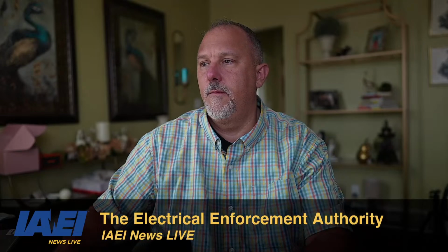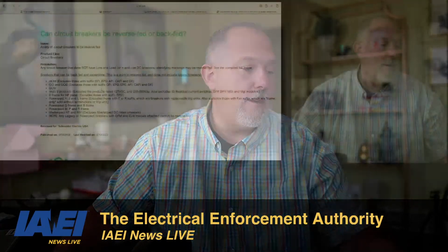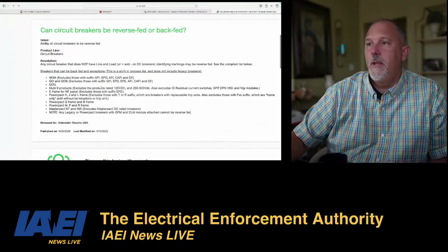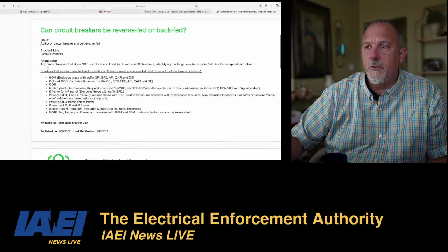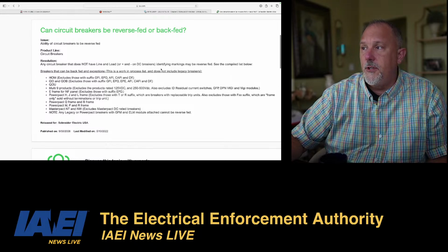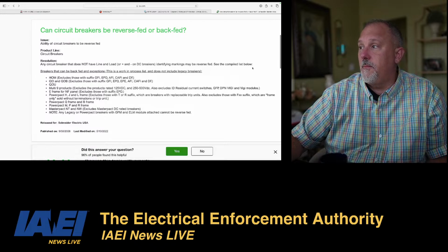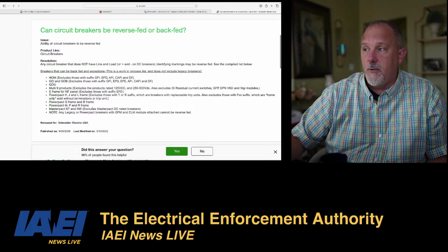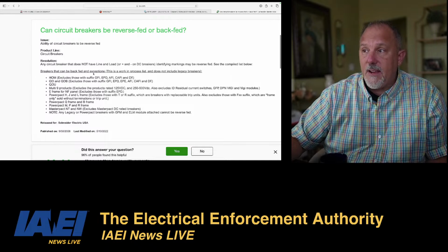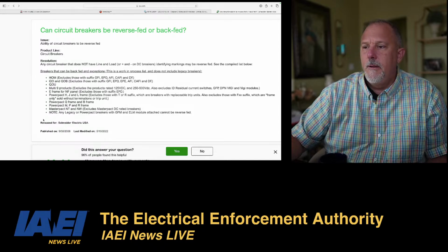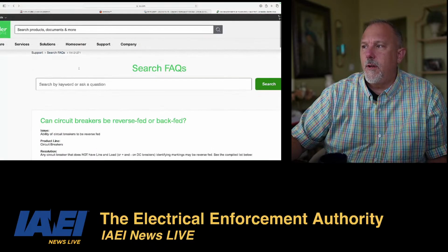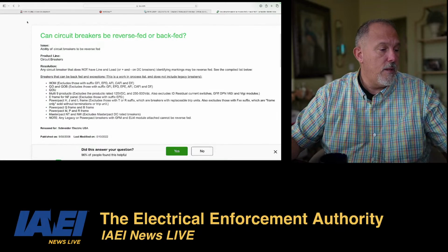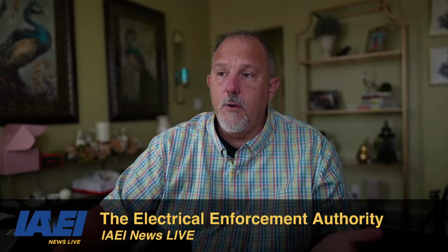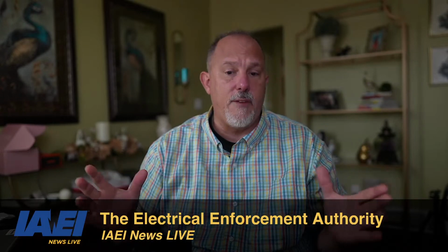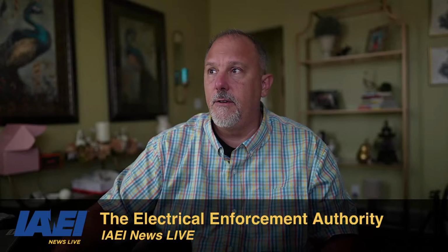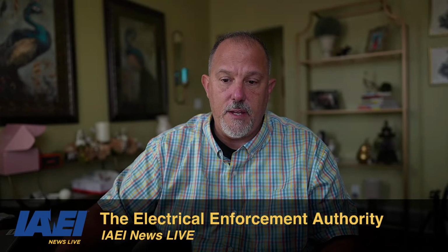All right. Here's a note from Schneider Electric. Ability of circuit breakers to be reverse fed. Circuit breakers, any circuit breaker that does not have line and load identifying marks may be reverse fed. See the compiled list below. And these are all of their models, breakers that can be backfed, and exceptions. So this is an FAQ created by Schneider, but I would say in general, if it's a circuit breaker, make sure it doesn't have line and load. That's going to be your indicator on whether or not you can backfeed.